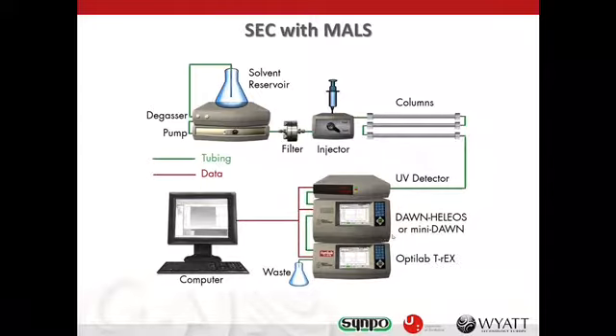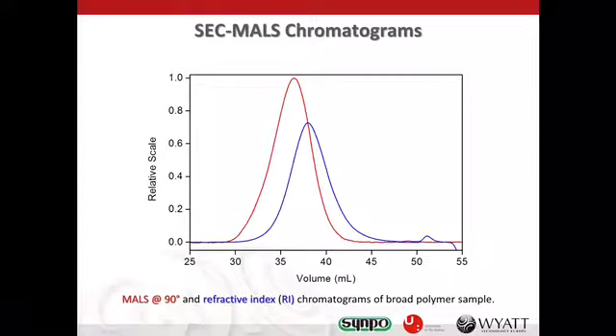The SEC-MALS setup is shown here. It is a regular SEC setup consisting of a pump, injector (typically an autosampler), and columns. Then we have mostly a refractive index detector — Optilab T-rEX in this case. We can have a UV detector for samples that absorb UV light. And then we add the additional multi-angle light scattering detector — in this case the EOS, Helios, or miniDAWN. With this setup, we can get absolute molar mass for molecules eluting from the SEC columns.